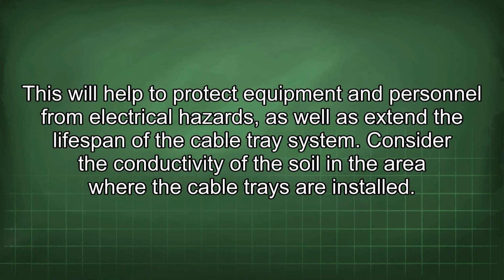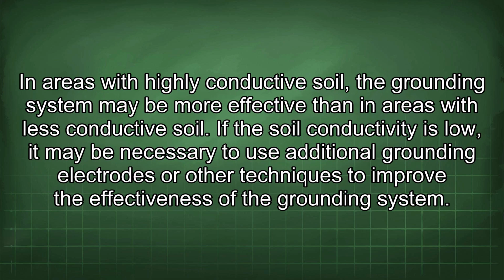This will help to protect equipment and personnel from electrical hazards, as well as extend the lifespan of the cable tray system. Consider the conductivity of the soil in the area where the cable trays are installed. In areas with highly conductive soil, the grounding system may be more effective than in areas with less conductive soil. If the soil conductivity is lower, it may be necessary to use additional grounding electrodes or other techniques to improve the effectiveness of the grounding system.